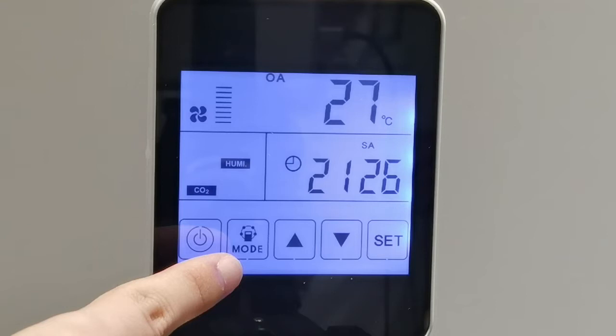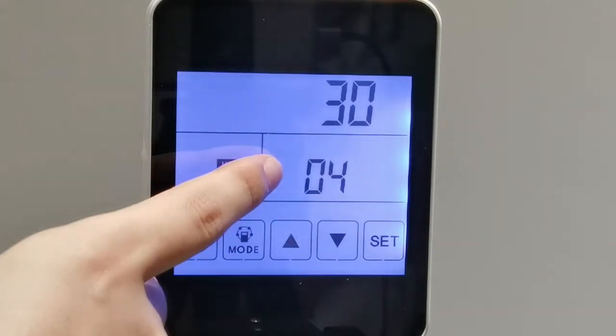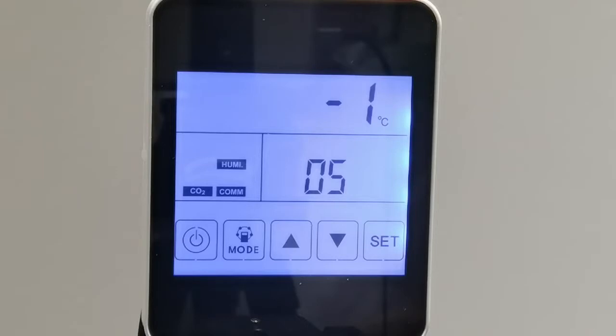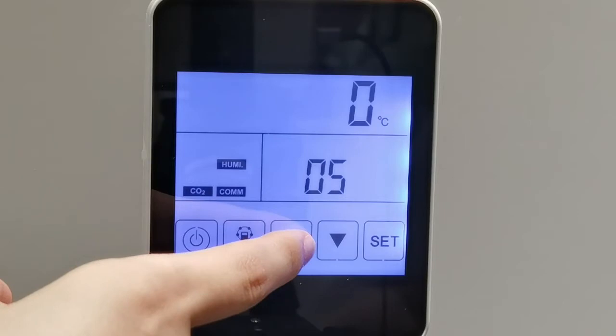It refers to the defrosting interval. It's related to the automatic defrost function. We will show you the detailed logic later. Okay, one more time to parameter 05. One more time, set value. Okay, parameter 05 refers to the defrosting entering temperature. We mean the exhaust air side of the heat exchanger temperature, which ranges from -9 Celsius degrees to 5 Celsius degrees. Yes, and the default is -1 Celsius degree.